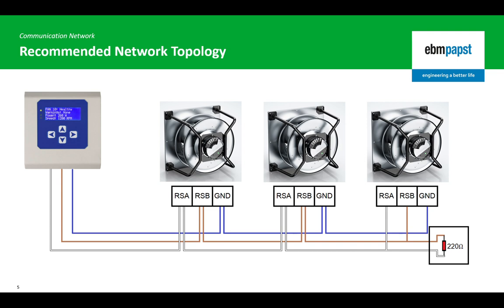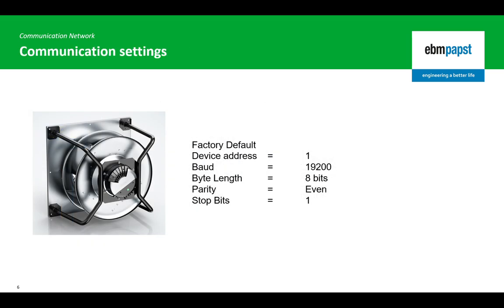Our recommendation for a network of EBM PAPST fans controlled by the MDC controller is to fit a 220 ohm resistor. Every standard EBM PAPST fan with Modbus functionality leaves the production line with the same parameters: Modbus device address 1, 19200 baud, 8 bits, even parity, with one stop bit.